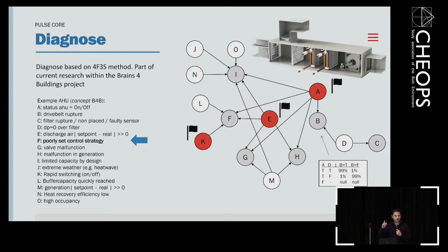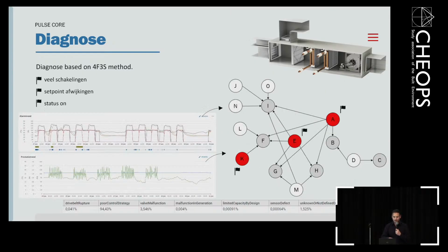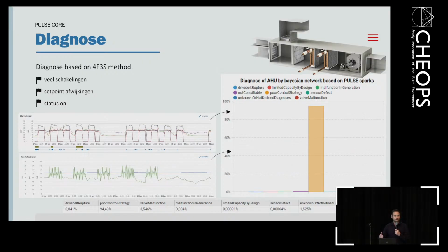So it's not really a fault, just a limitation set in the design phase. Or maybe you see a lot of pendelgedrag—rapid turning off and on, rapid switching of the installation's status—well, that's probably a poor control strategy. Just looking at this data can be quite complicated, but by using Pulse you can go directly to what is going on. The left graph shows a lot of raw data, but on the right side, where this analysis has been done, it shows there's a high chance of a poor control strategy in this HVAC system.